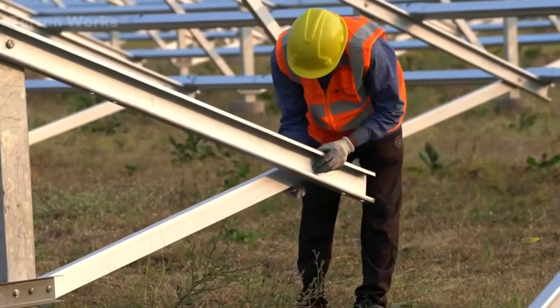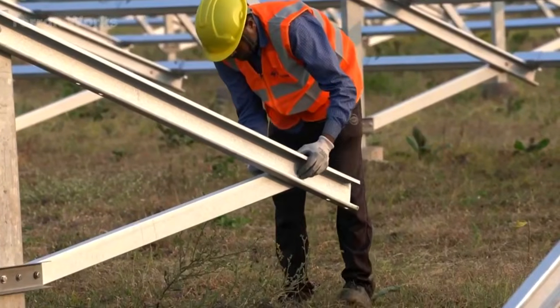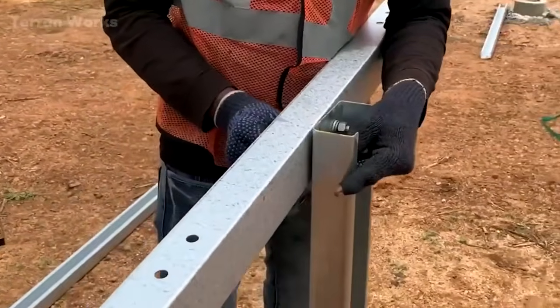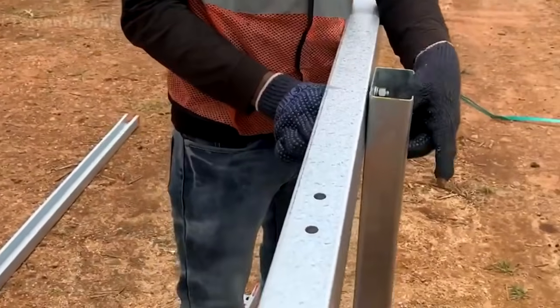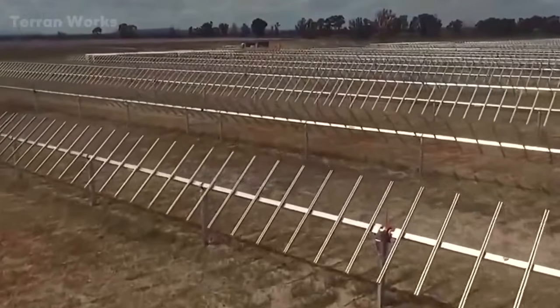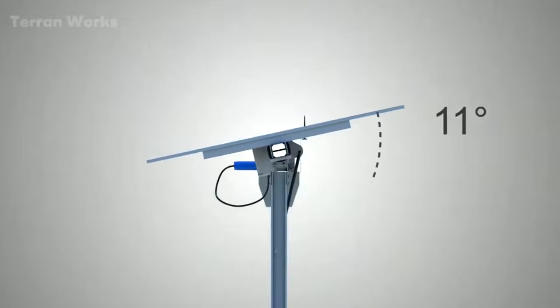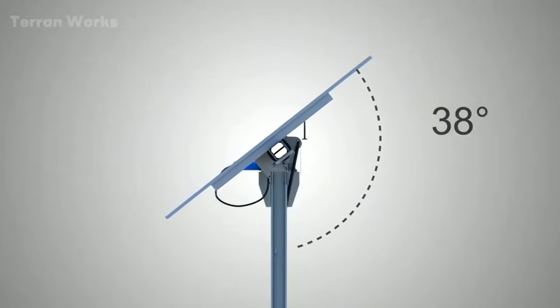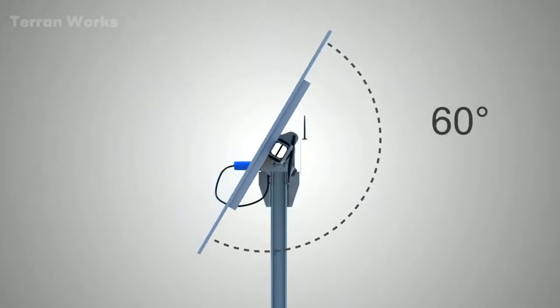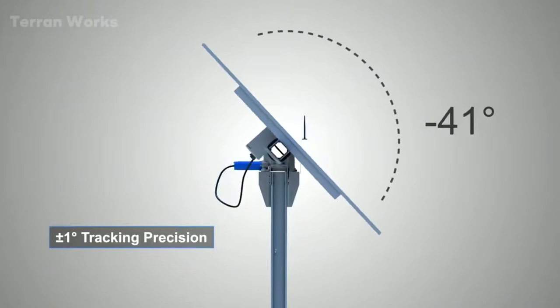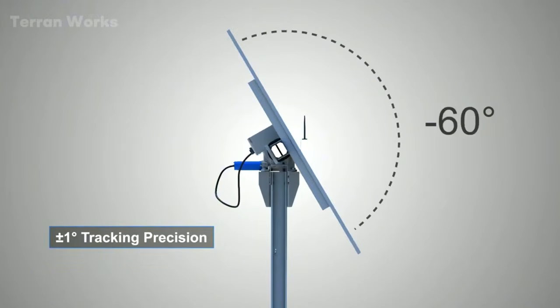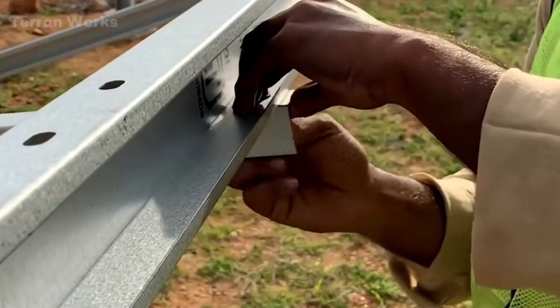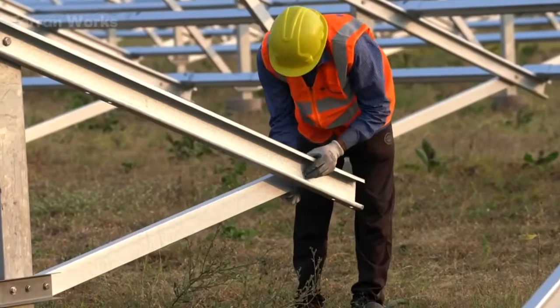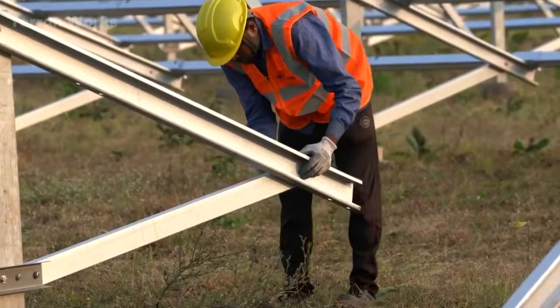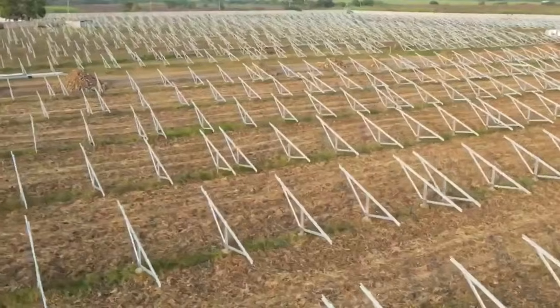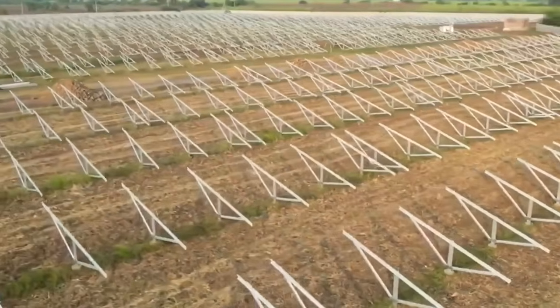Many modern fields add movement to this metal. A single-axis tracker rotates the row around a longitudinal tube, using drives and linked supports. At sunrise, the table tilts east. By afternoon, it is turned west to improve the incidence angle. The gain is large. Against fixed racks, tracking can increase electricity generation by 15 to 25%. For a 10 gigawatt project, that boost equals 1 to 2 gigawatts of added capacity without another station. The rows start following the sun, while crews move to module mounting, the grounding circuit, and operation in sand.